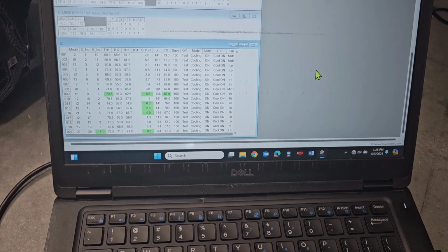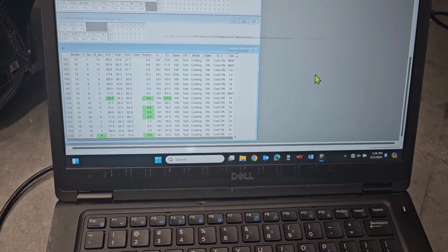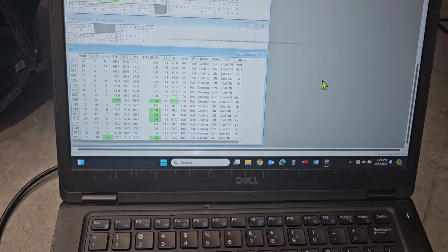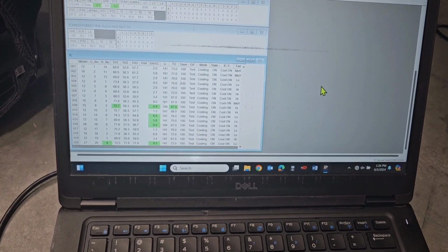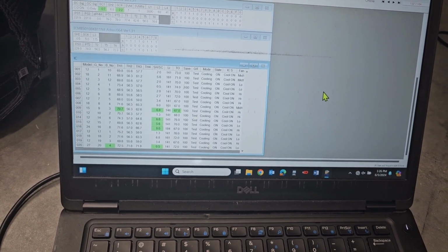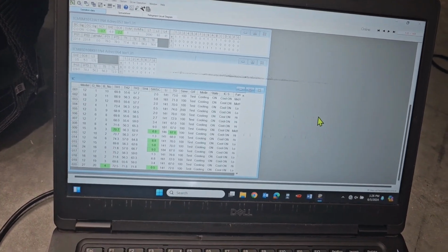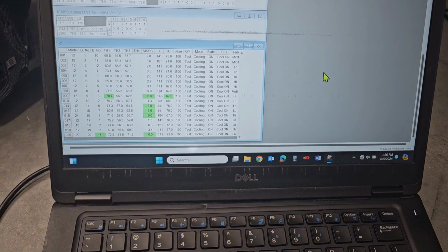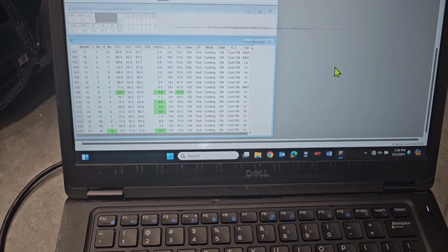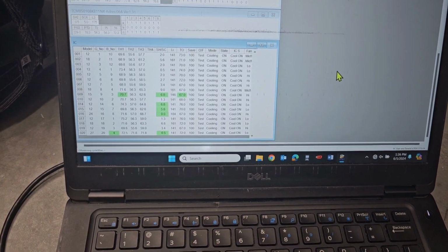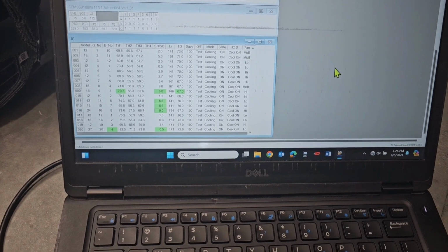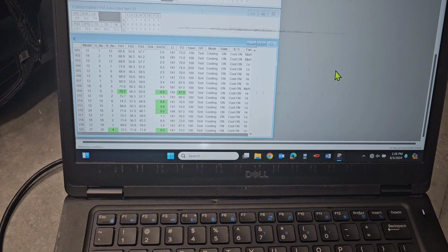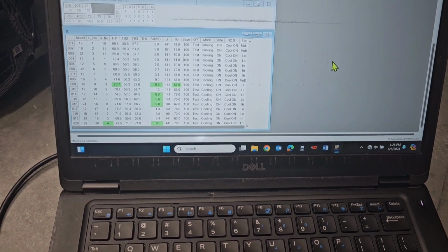So you have to continue to ask yourself, okay, now how can I prove it even further, right? So after watching it for a while, everything was running fine. I wanted to check to see, now that it's been running for a while in full test mode, if I open these 3 back up, what happens? And nothing really major changed. It was still looking decently good, right? My superheat didn't come up much. Everything looked more or less the same.